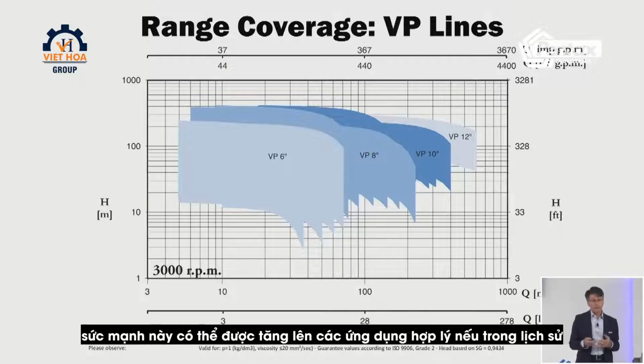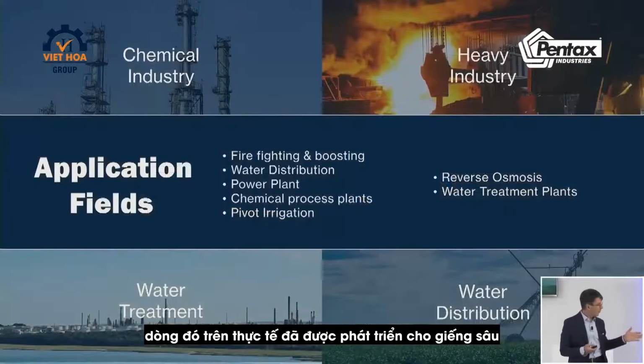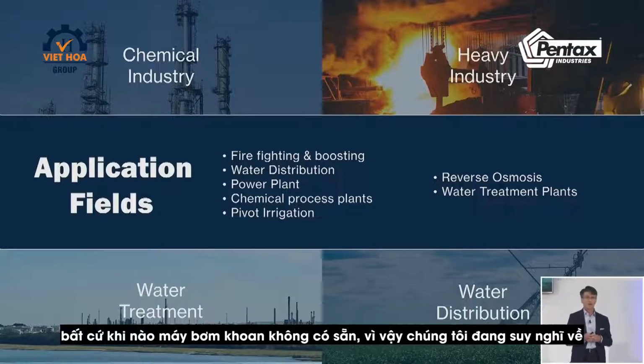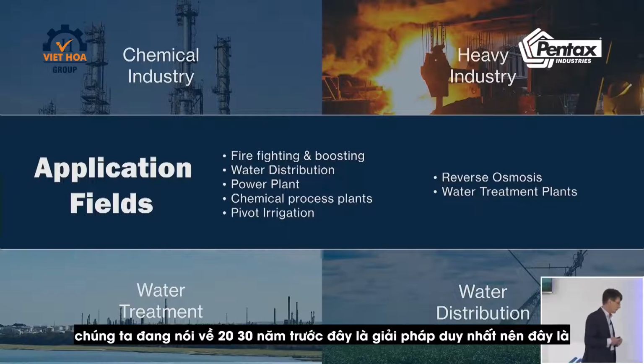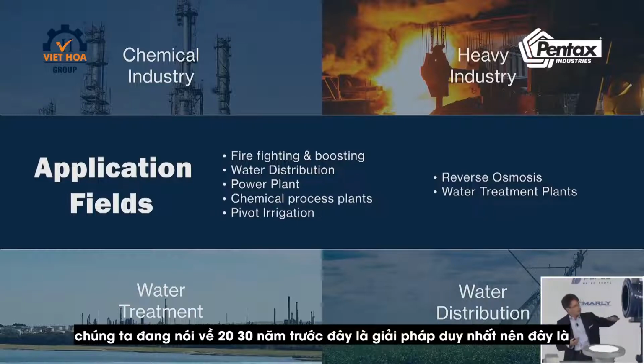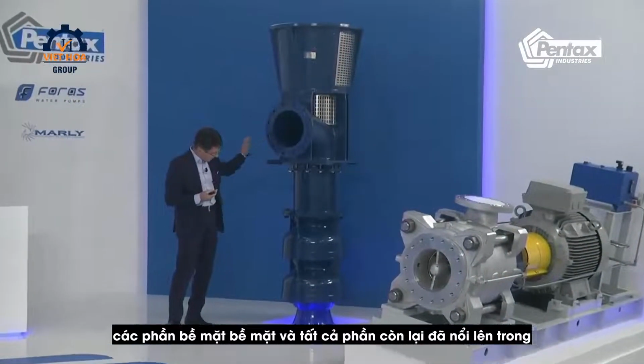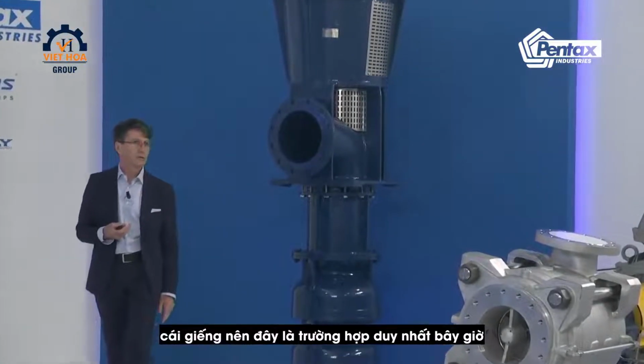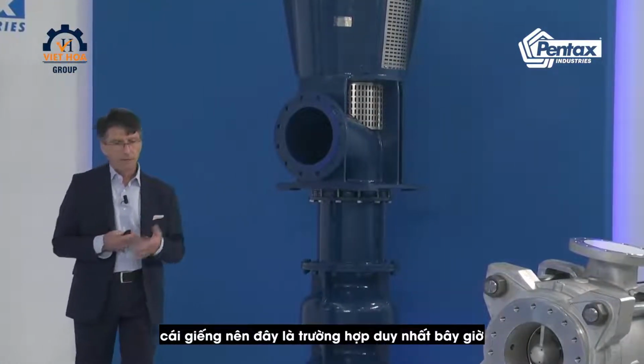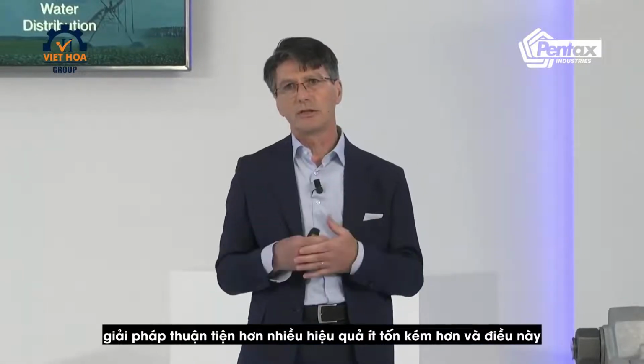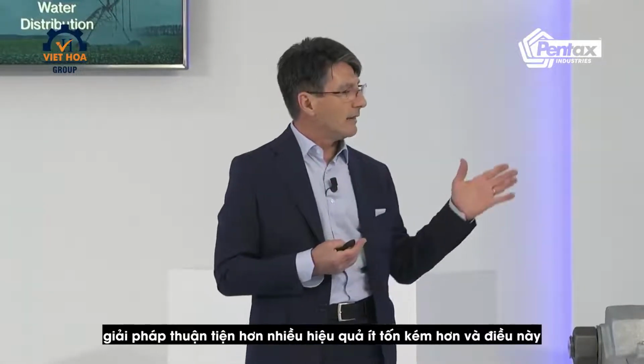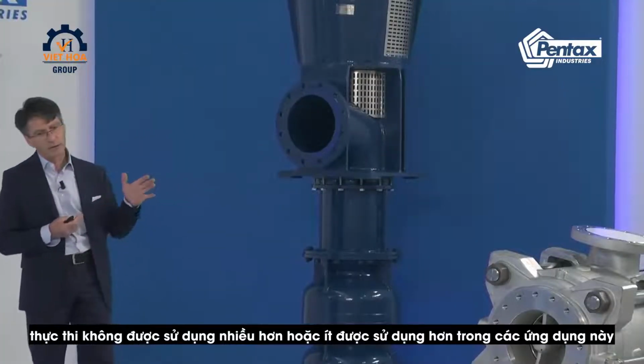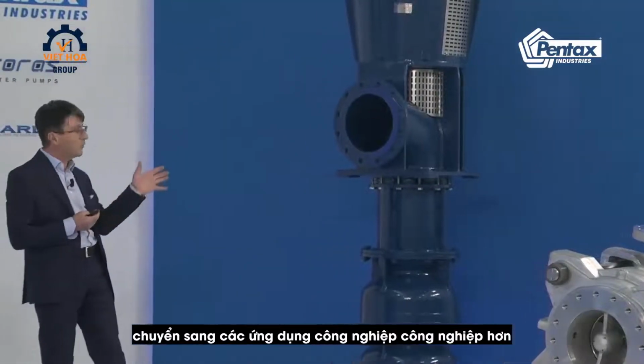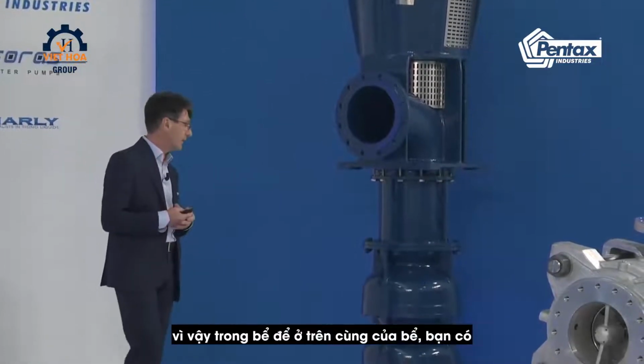Applications. Well, historically that line was practically developed for deep well, whenever the borehole pumps were not available, so we are talking about 20, 30 years ago, this was the only solution. So this was the surface part, and all the rest was immersed in the well. So this was the only case. Now, the borehole solution is much more convenient, efficient, less expensive, and this execution is not used anymore or less used in this application. It's moving into more industrial applications, so in tank.